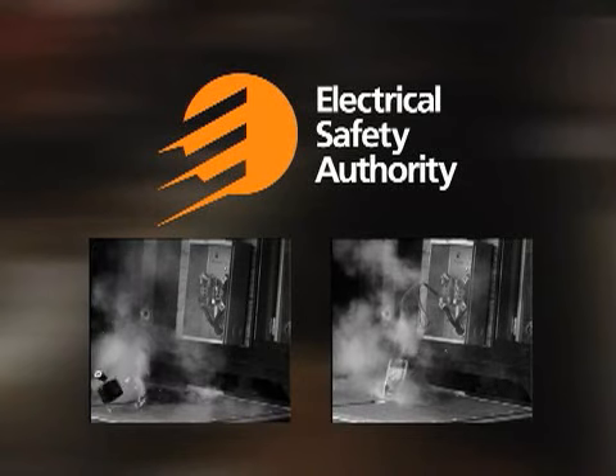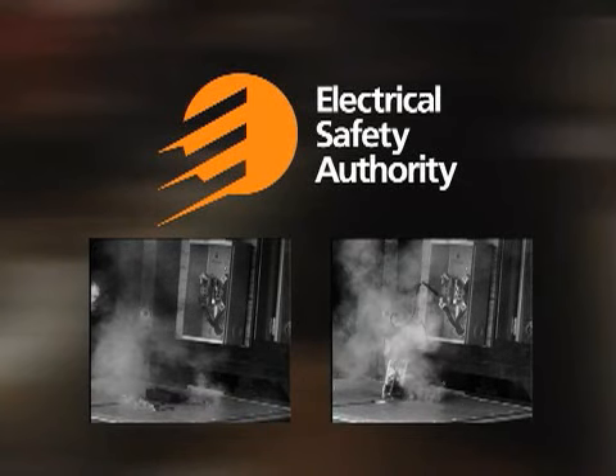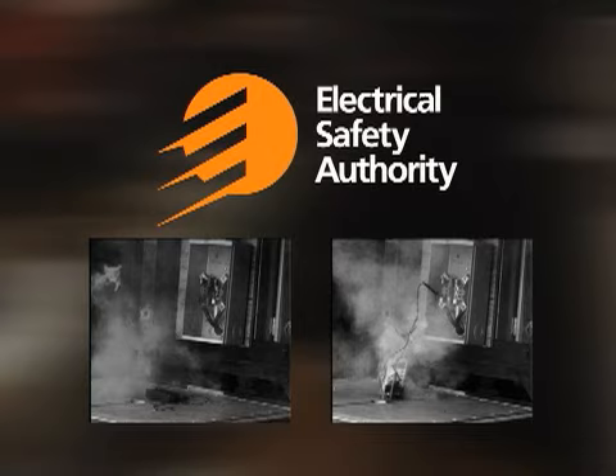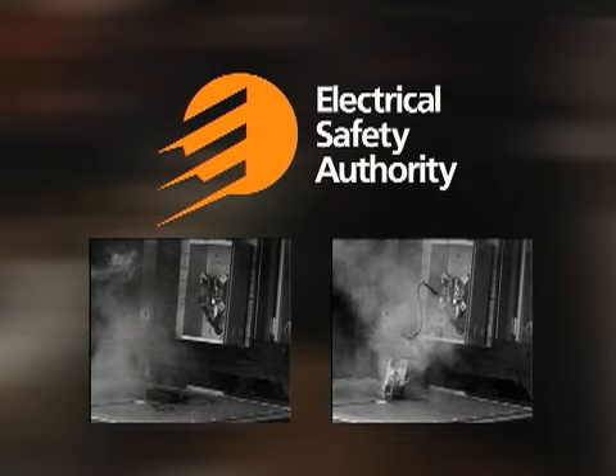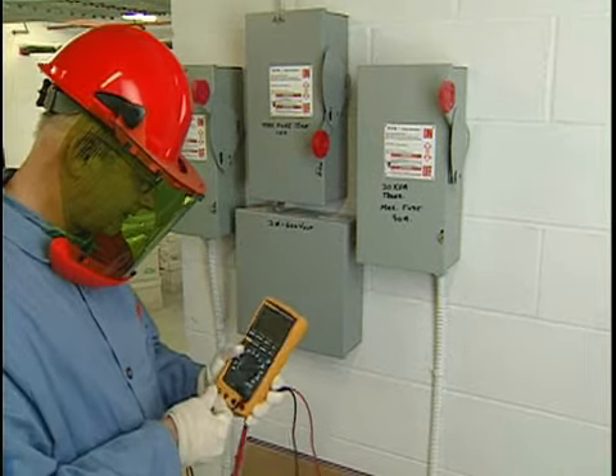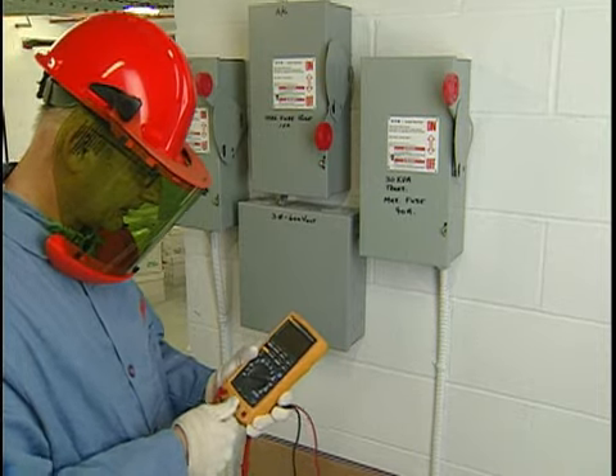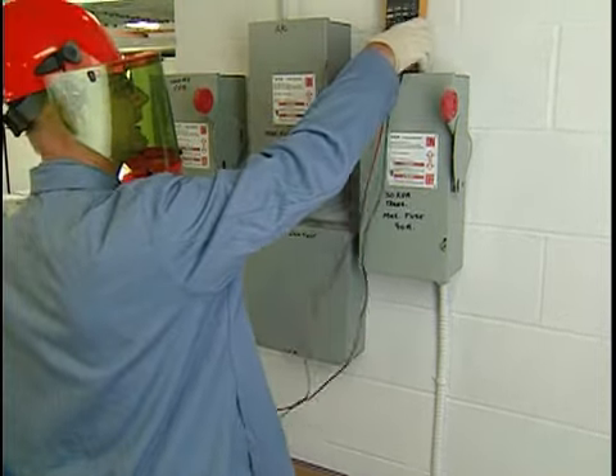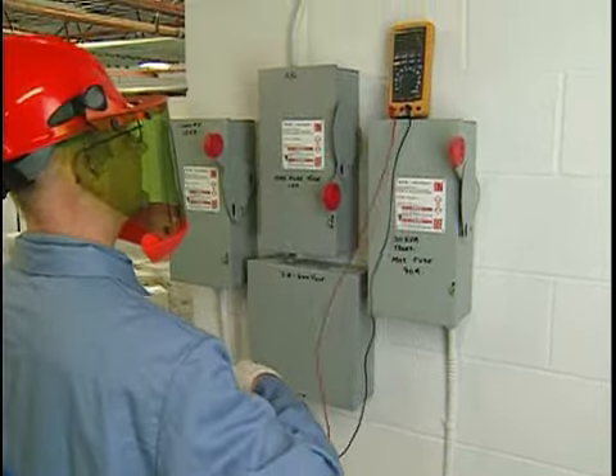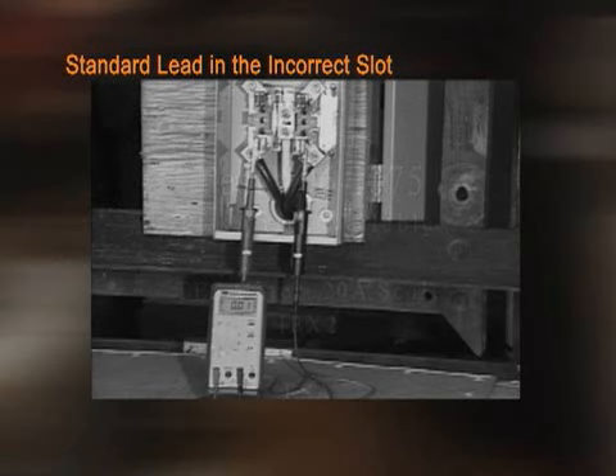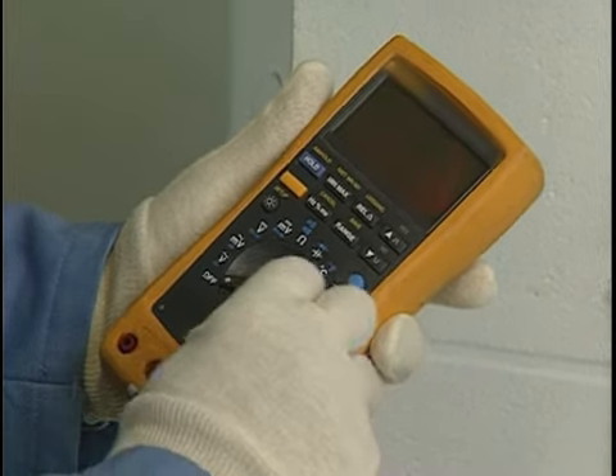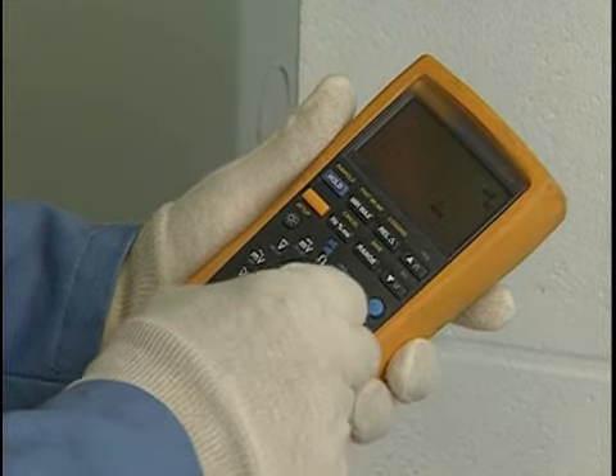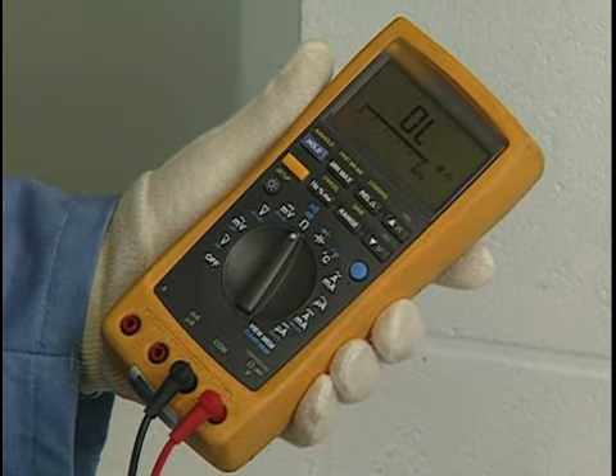Fused leads reduce arc explosions created by meter failures in up to 90% of the time in simulated tests. Meters can fail when the leads are in the ammeter or ohmmeter slots, creating a short circuit across phases when used to measure voltage. Meters can fail when the selector switch is on the wrong setting when put into contact with an energy source.